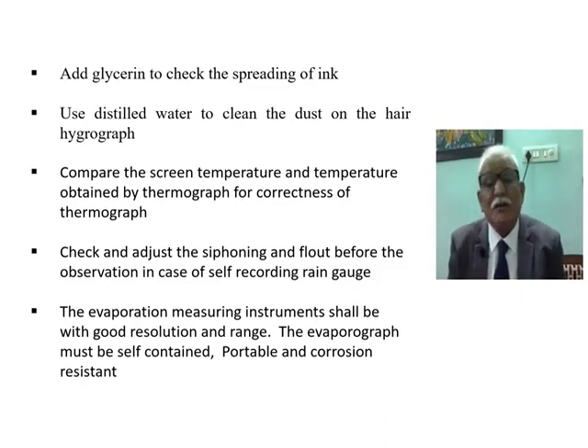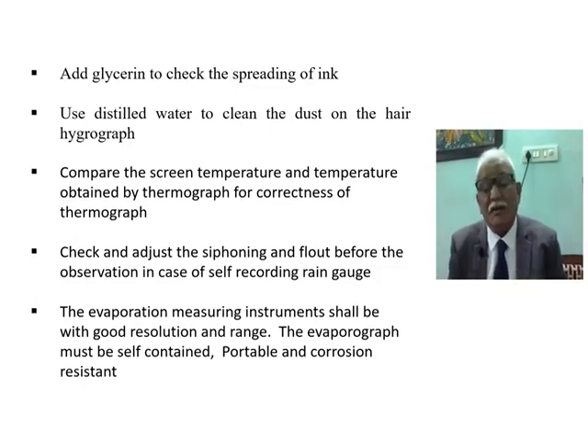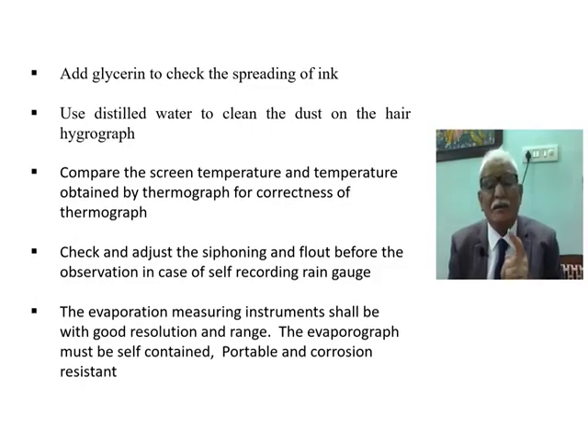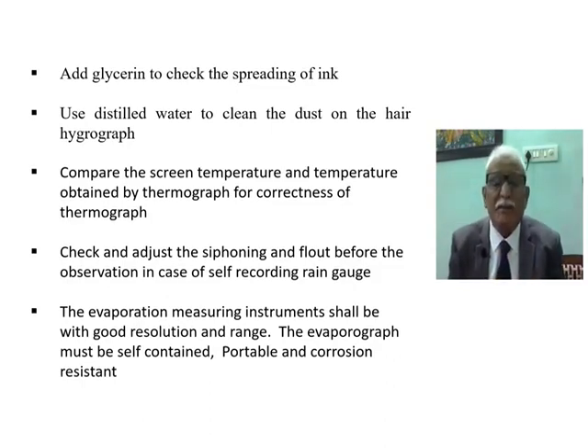Check and adjust the siphoning mechanism and the float before observation in case of the self-recording rain gauge. The self-recording rain gauge records the quantity and time of occurrence of rainfall, so the siphoning mechanism and float should always be properly maintained. Evaporation measurement instruments shall have good resolution and range.